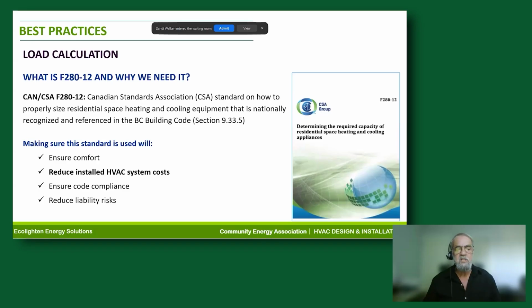We want to reduce installed HVAC system costs, so we don't want to oversize the system. There's no upside to that. It's going to cost more, it's not going to work as effectively, it could short cycle, and it will shorten the system's lifespan with more maintenance and repair costs. There are a lot of downsides to not sizing properly, but no upside.